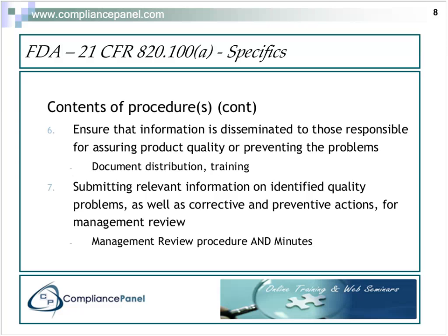Now remember that the results of your management reviews are not viewable by FDA. So it's incumbent upon you to make sure that you have a summary document that is reviewable by the FDA that shows that during your management review, you reviewed your CAPAs and which CAPAs those were. A summary document or an agenda or minutes. Something like that usually suffices as far as the FDA is concerned.